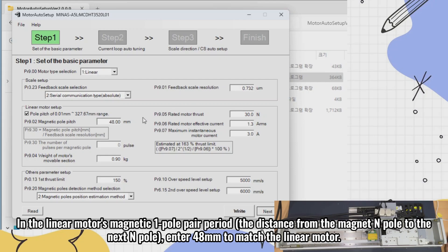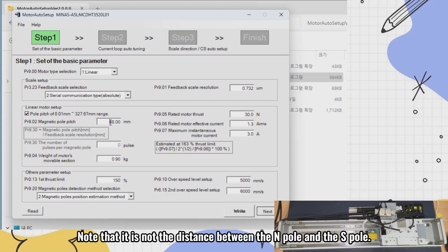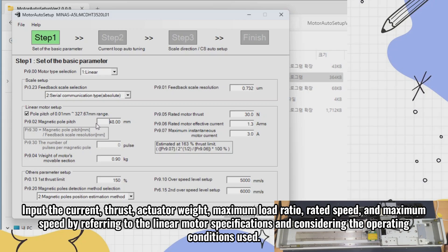In the linear motor's magnetic one pole pair period — the distance from the magnet N pole to the next N pole — enter 48 millimeters to match the linear motor. Note that it is not the distance between the N pole and the S pole. Input the current, thrust, actuator weight, maximum load ratio, rated speed, and maximum speed by referring to the linear motor specifications and considering the operating conditions.